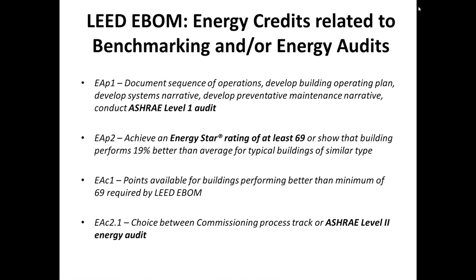So for those of you who aren't familiar with the LEED EBOM rating system, there's two real prerequisites required for the energy and atmosphere credits. Prerequisites meaning that in order to get LEED certification, these are things that you have to do, that there's no credit associated with them. These are mandatory requirements, the first being EAP1. That's the typical notation to refer to prerequisite 1 in the energy and atmosphere category. Every building, existing building, going through LEED certification must have an ASHRAE Level 1 energy audit conducted. We'll get to that in a few minutes as to what the different levels of ASHRAE energy audits are. But as a prerequisite, every building has to have an ASHRAE Level 1 walkthrough audit completed.